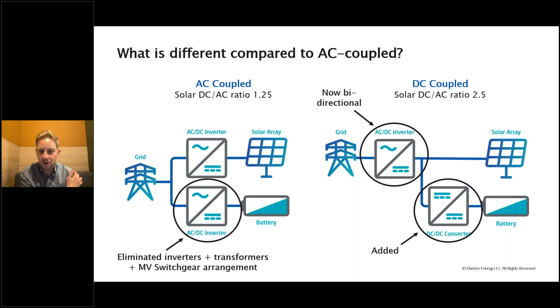But there are trade-offs. You also have to procure DC to DC converters, because the voltage from the solar project changes throughout the day, and the batteries need to adjust their voltage to match the solar, since they're connected to the same bus bar on the inverter. These projects get more complex as they become more intricately interrelated—doubly so for software and controls, since you can get complicated feedback loops on grounding and control. If the voltages don't match, the system ends up tripping out all the time. These setups are not straightforward, particularly with a self-integration route, as opposed to buying a complete technology solution from someone like Fluence.